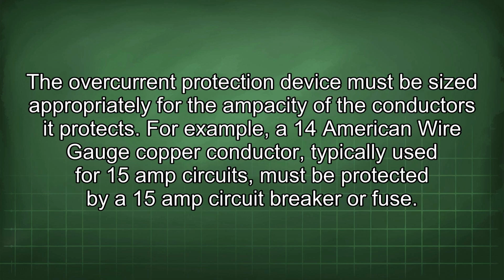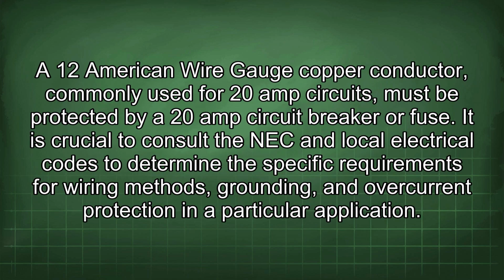The overcurrent protection device must be sized appropriately for the ampacity of the conductors it protects. For example, a 14 American wire gauge copper conductor, typically used for 15 amp circuits, must be protected by a 15 amp circuit breaker or fuse. A 12 American wire gauge copper conductor, commonly used for 20 amp circuits, must be protected by a 20 amp circuit breaker or fuse.